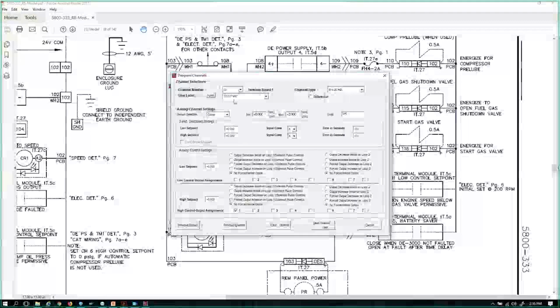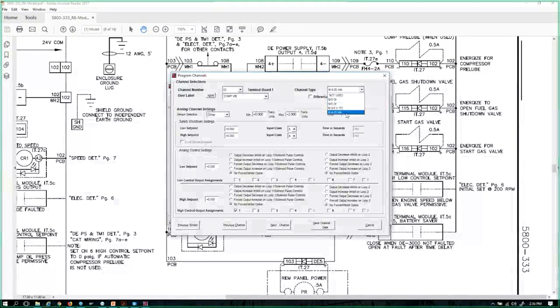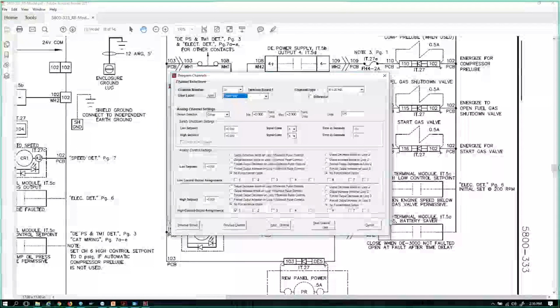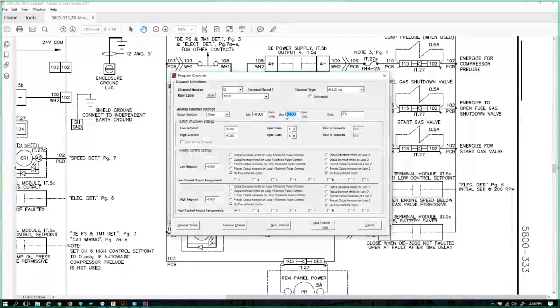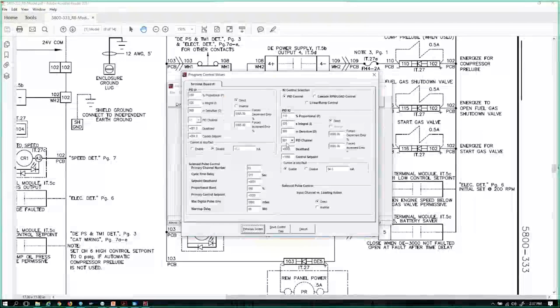Oops. Well, we did for a brief moment in time. I think at one point we had called this field pressure. And we had scaled it somewhere in the neighborhood of 0 to 2000. So this would be a perfectly acceptable arrangement if I wanted to use analog output 2 to look at the field pressure for a recycle valve application. And I'm okay at this point.